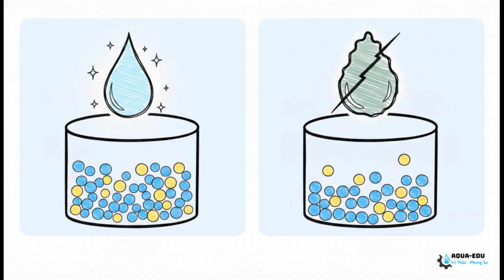So the crucial takeaway here is understanding our normal operating baseline. For that intimate mixing to work flawlessly, the volumetric ratio of cation to anion resin has to be perfectly balanced. Depending on your specific feed water, that expected ratio is usually 1:1 or 1:1.5. When this ratio is perfectly dialed in, your system is going to reliably yield pristine water with a resistivity well above 15 megaohms per centimeter. That right there, that is the gold standard we are always aiming for.